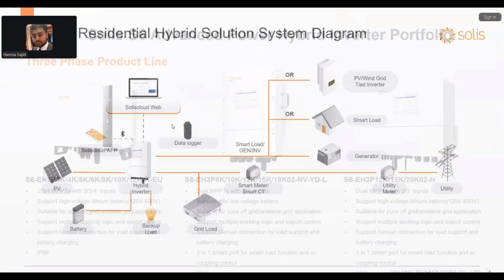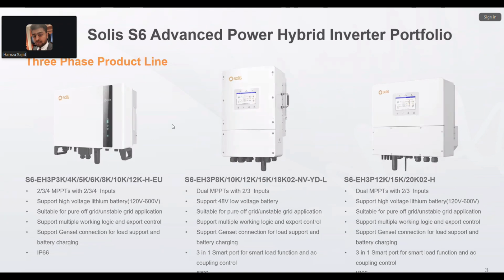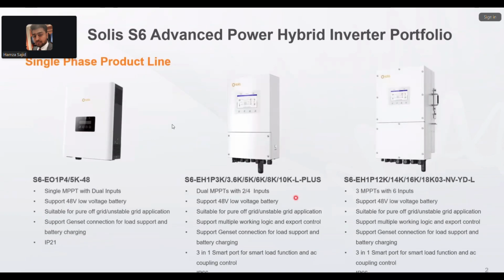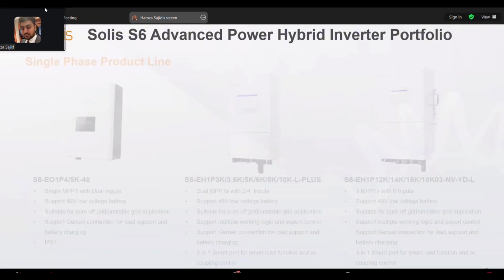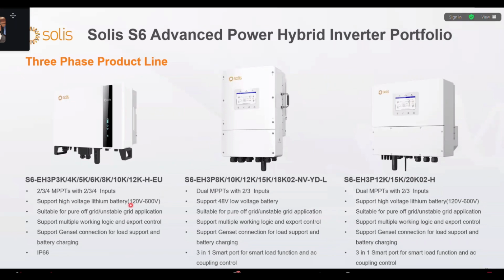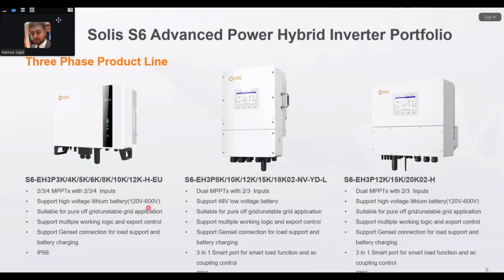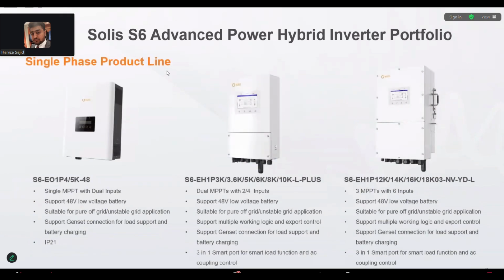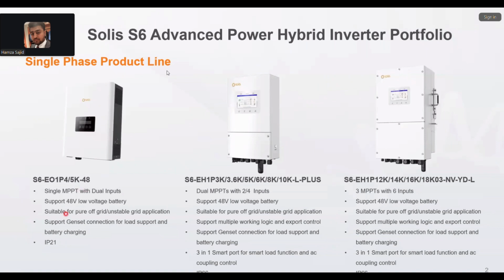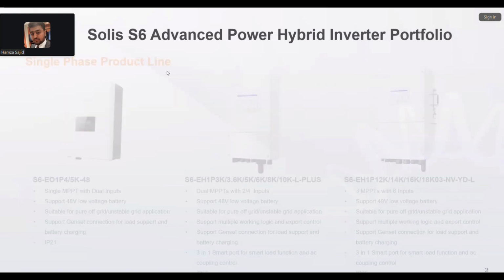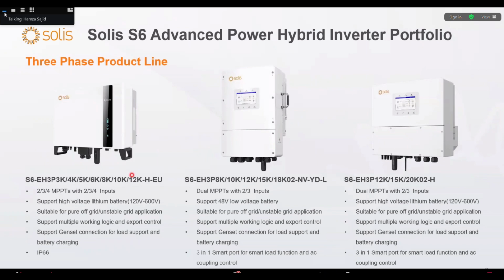So let me tell you a few things. When I am talking about high voltage, that means the battery input voltages will be higher than 48 volts. The battery voltages will start from 120 volts to 600. If I am talking about low voltage, that means the battery voltage range is from 40 volts to 60 volts, and the nominal voltage is 48 volts. So these three categories are the low voltage single phase, and these two are the high voltage, and the middle one is the three phase low voltage system.